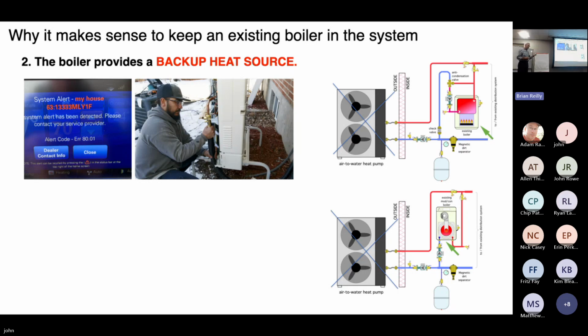It doesn't necessarily require anybody to throw a switch. If it detects that there's a load requirement, in other words, the building is calling for heat, and it's trying to get it from the heat pump, but the heat pump is off, it's going to automatically switch to the boiler. Some systems will switch based on outside air temperature. There are controls that will do that. And you actually have inputs on fuel cost and COP performance of the heat pump. They will calculate at what point it is less expensive to operate the boiler than it is to operate the heat pump. And they'll simply switch over.